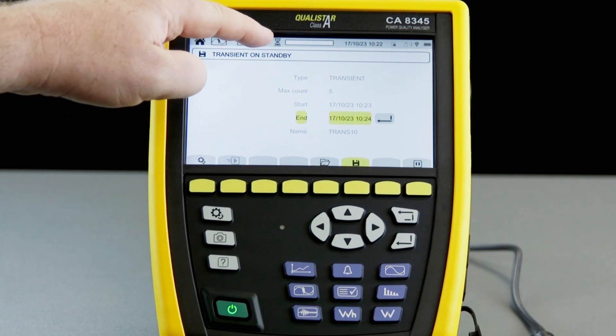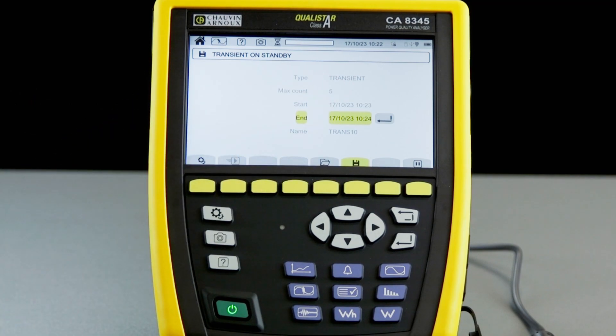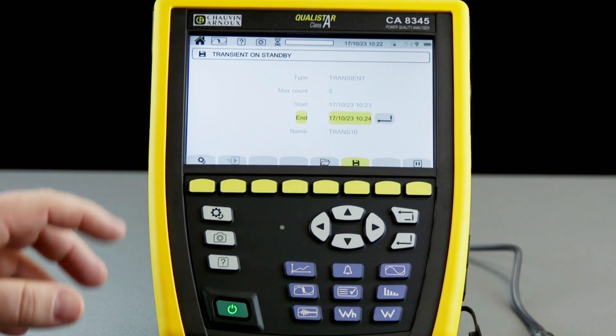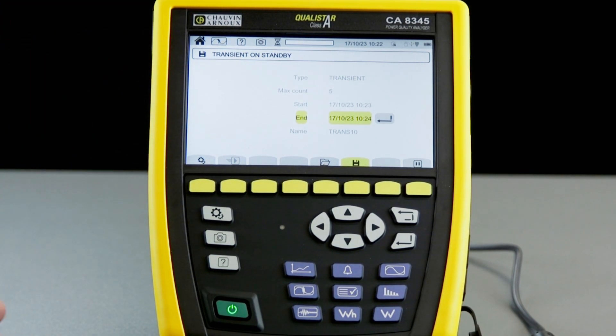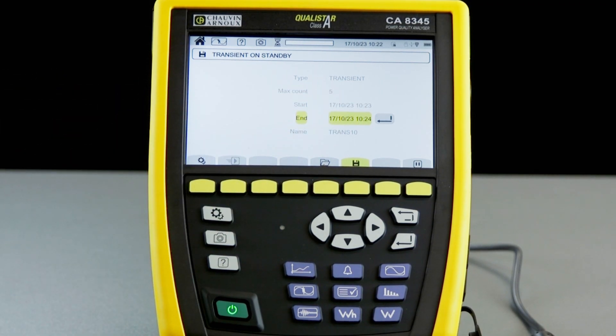You will see the egg timer icon at the top of the screen while the CA-8345 is waiting for the session to start. Once the session starts, it will look for transients meeting the threshold limits we've pre-programmed, and when it captures five of those it will end the session. If no events are captured, or it doesn't reach five before the end time, it will end the session automatically.